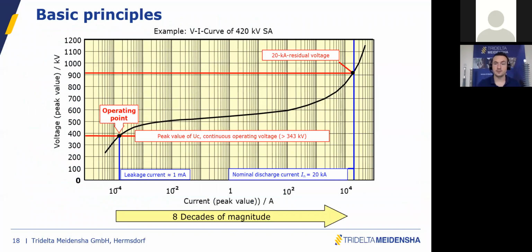On this diagram, I'm sure you're familiar with that. This is the non-linear characteristic of the MOV, of the zinc oxide technology. So the voltage-current characteristic, with current on the x-axis and voltage on the y-axis. It's important to split this diagram in two parts. On the right side you have the transient overvoltages, switching and lightning, and on the left side you have the operating area and temporary overvoltage, which are two different behaviors for the arrester.